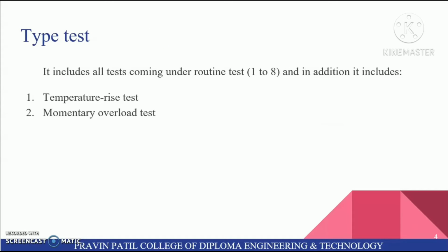So next is the type test. It includes all tests coming under routine test, that is 1 to 8, and in addition it includes temperature rise test and momentary overload test.